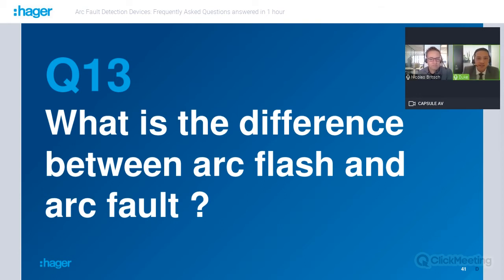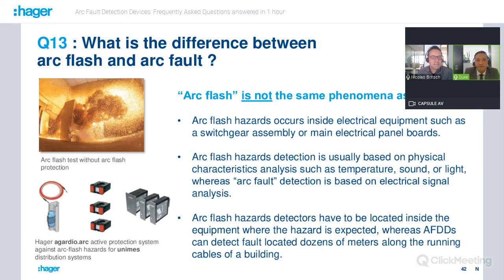Now the next question, number 13. What is the difference between arc flash and arc fault? Okay, this is also a question that we have sometimes. Arc flash is not the same phenomenon as arc fault. Arc flash hazards occur inside electrical equipment, such as a switchgear assembly, for example. And arc flash hazard detection is usually based on physical characteristics analysis, such as the temperature, the sound, the light, whereas arc fault detection is based on electrical signal analysis, as I told you before. And arc flash hazard detectors have to be located inside the equipment where the hazard is expected, whereas AFDDs can detect faults located dozens of meters along the running cables of a building.